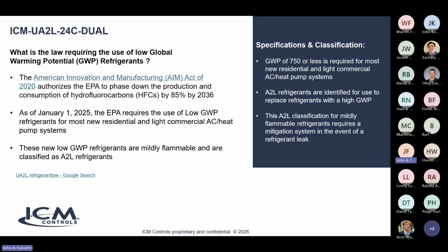And as of January 1st of 2025, the EPA now requires the use of low GWP refrigerants for most residential and light commercial applications. However, these new low global warming refrigerants, like I mentioned, are slightly flammable. They're mildly flammable and are classified as A2L refrigerants, okay? Because of that mild flammability rating.